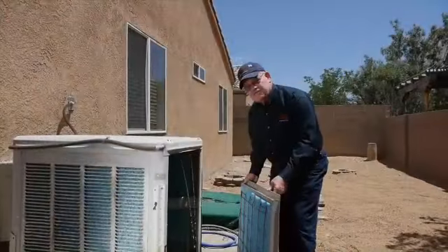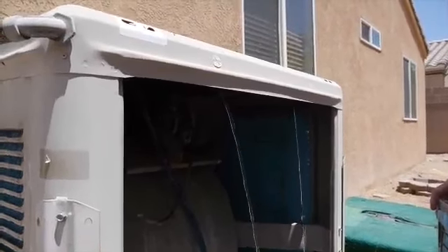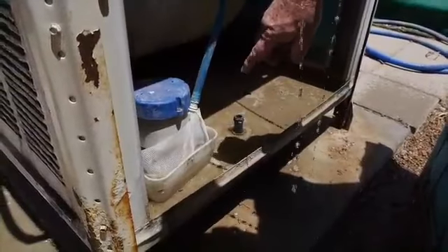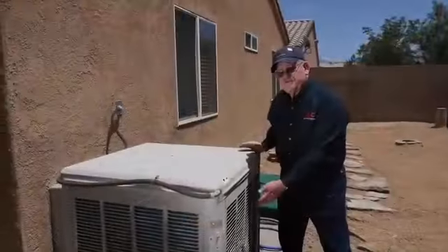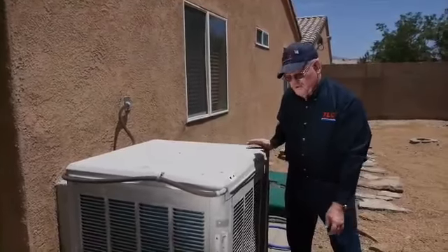Another thing you want to check is to make sure that your pump is putting out the proper amount of water to keep the pads wet. The little screen around the pump becomes clogged with aspen fibers or other debris over time, so make sure that's kept clean. So once you've ensured that the pump is putting out sufficient water, check to make sure that the pads are getting wet.